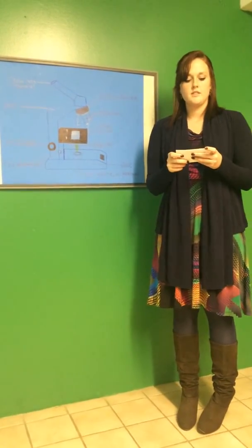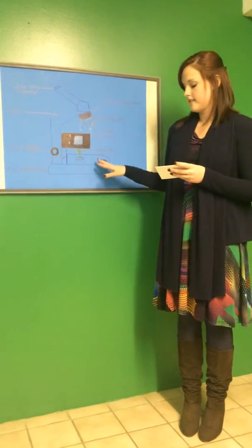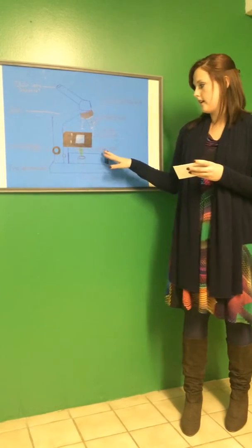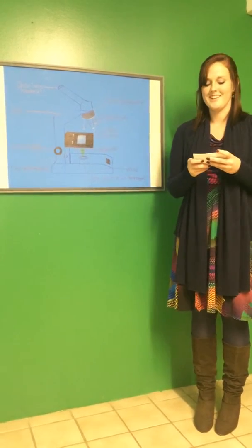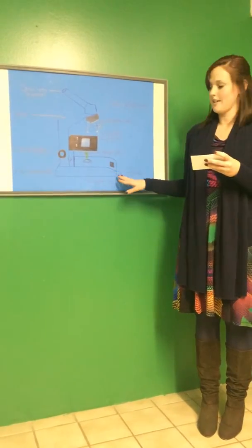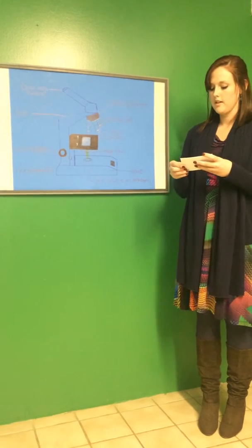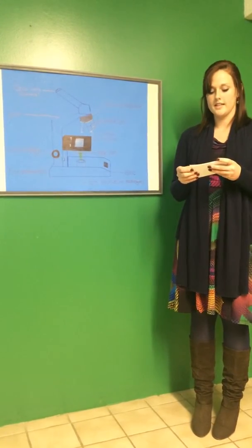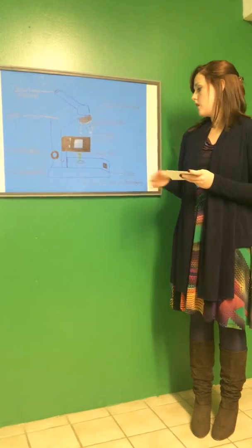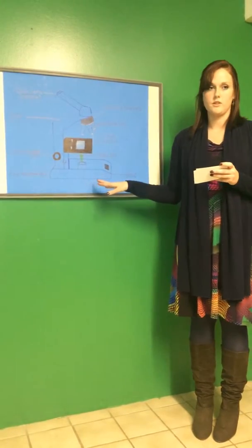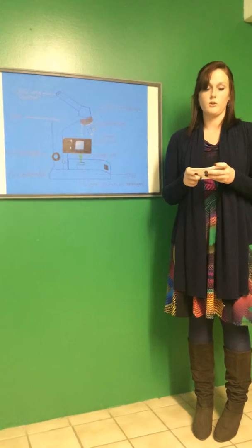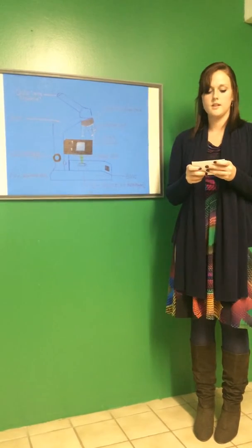The last thing you need to know is how to control the brightness and light concentration on the specimen. Most specimens are going to use bright light with the iris diaphragm all the way open. However, if you're viewing live specimen or unstained specimen, you might want to close your iris diaphragm so that there's less light or maybe even no light, depending on the specimen of choice.